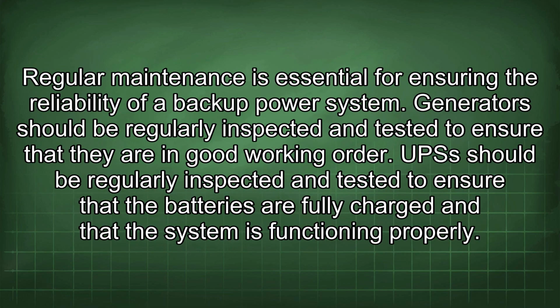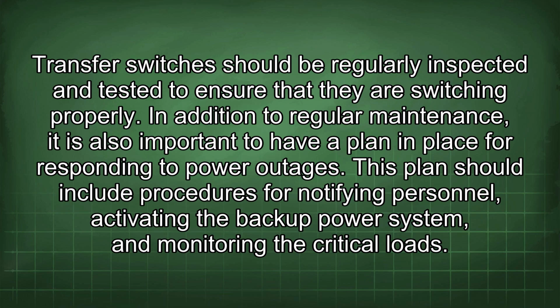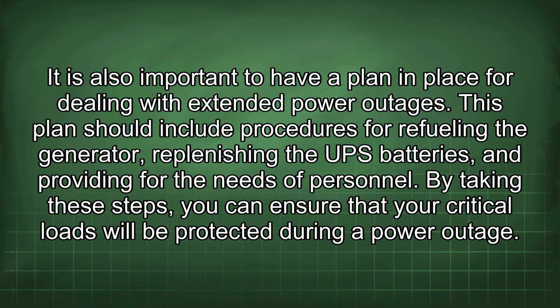Regular maintenance is essential for ensuring the reliability of a backup power system. Generators should be regularly inspected and tested to ensure that they are in good working order. UPS should be regularly inspected and tested to ensure that the batteries are fully charged and that the system is functioning properly. Transfer switches should be regularly inspected and tested to ensure that they are switching properly. In addition to regular maintenance, it is also important to have a plan in place for responding to power outages. This plan should include procedures for notifying personnel, activating the backup power system, and monitoring the critical loads. It is also important to have a plan in place for dealing with extended power outages. This plan should include procedures for refueling the generator, replenishing the UPS batteries, and providing for the needs of personnel. By taking these steps, you can ensure that your critical loads will be protected during a power outage.